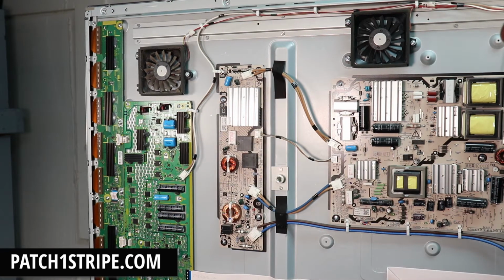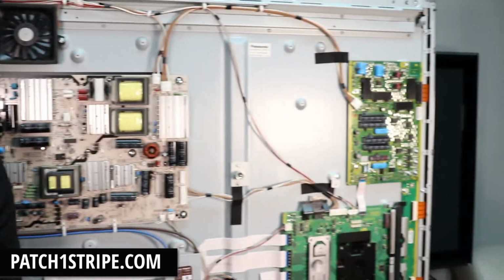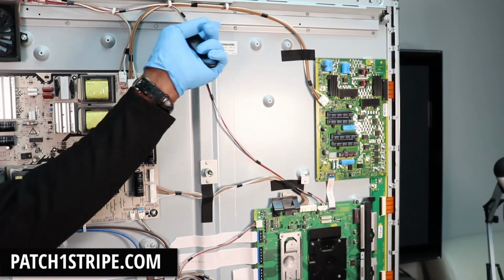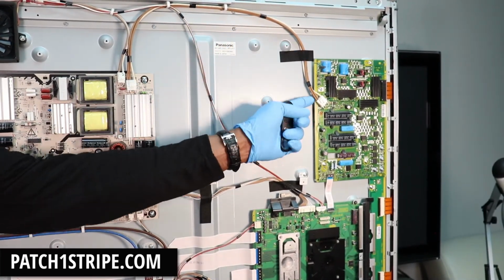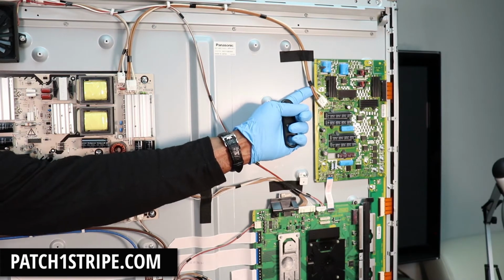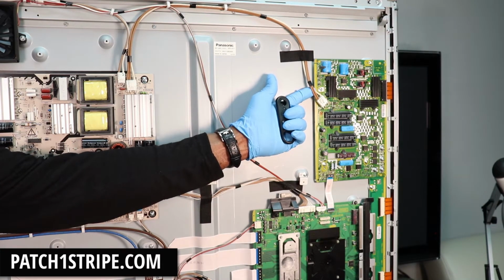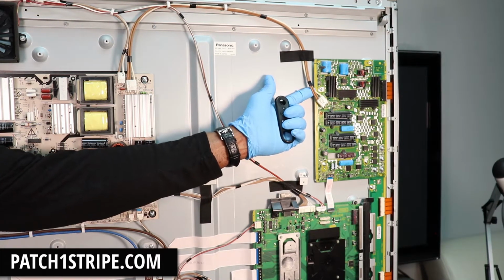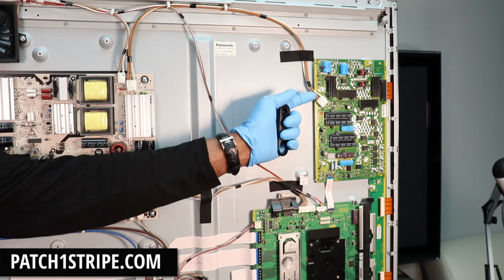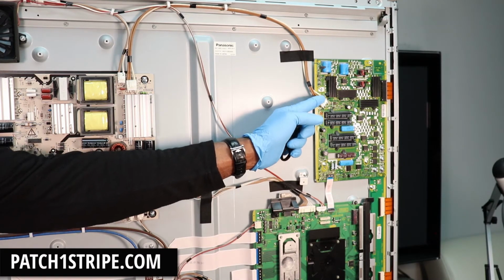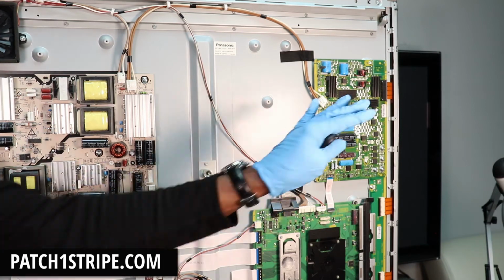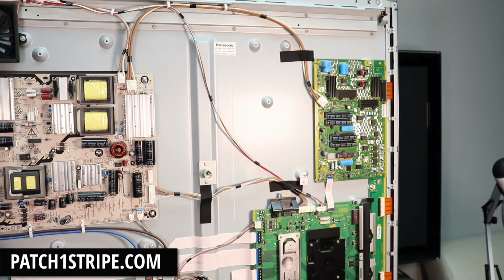I did the same thing with this particular board, and the two pins were open between them, no continuity, so I knew this board was good as well. When I went over to the other side of this unit, I checked for continuity again, and they were open between these two pins, so I knew I didn't have a short to ground there.